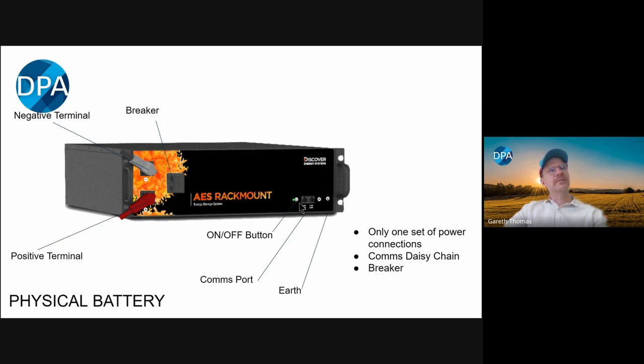There's an on-off button here. When you press it, there's a contactor inside the battery on the BMS that turns on and off. That's an interesting point, because a lot of other batteries' BMS just turns off the supply electronically with FETs - it doesn't actually mechanically break it. Whereas the contactor inside the Discover batteries has two big contactors in series with each other, so when it's off, it's off - that's its default state. The coil needs to be engaged by the battery for it to turn on, so it offers a lot more protection than the breaker alone against any sort of short circuit. We've got the comms ports here.